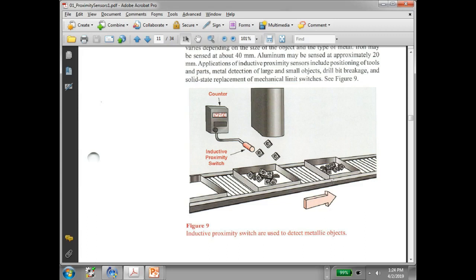Yeah, the more ferrous it is, the better it would detect it, right? So aluminum, it'll detect aluminum, but aluminum is almost not ferrous at all, right? So with aluminum, you're going to have to get real close to it. But a big chunk of steel, even though they're exactly the same size, this is what we did up in Tennessee, which was pretty neat. They had a bunch of tiny plates, all exactly the same size and the same thickness. Then we moved them up to the inductive sensor to see how close we had to get. We had a little ruler.